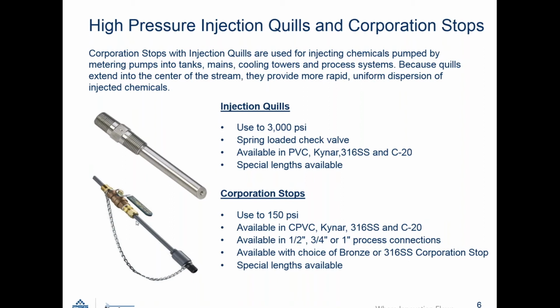the system can't be stopped, or the water line cannot be shut down. These corporation stops are used in what we call a hot tap. A hot tap, just the description would be like a saddle going around a pipe, and the bronze valve would be installed on the saddle, where the hot tap, which is a drill basically, goes through our valve and cuts a hole into the pipe while the system's still in use. And when the hole is drilled and pulled out, you can shut off this valve and pull out your hot tap, and then you can put our quill back into the valve, open up the valve, and put it right into the system.